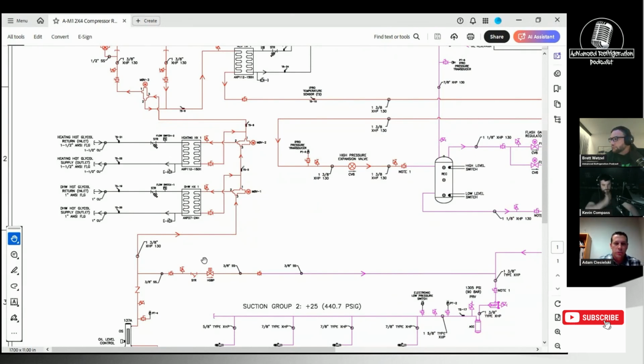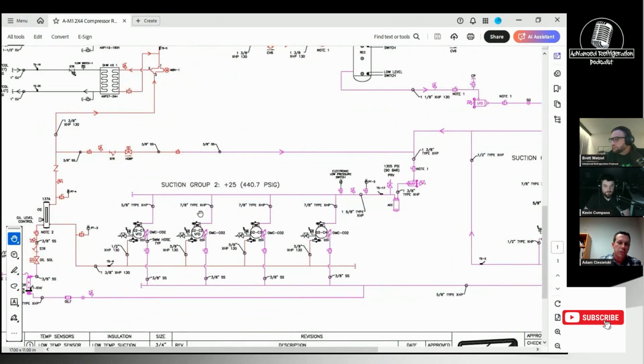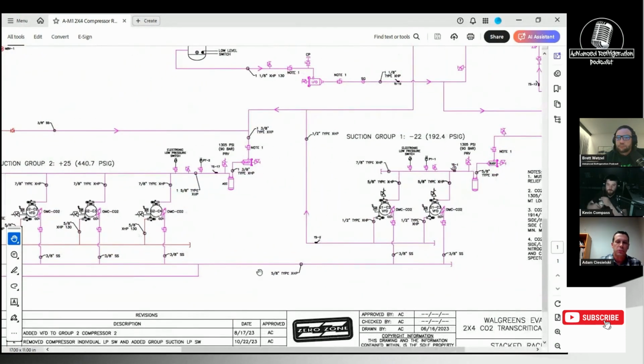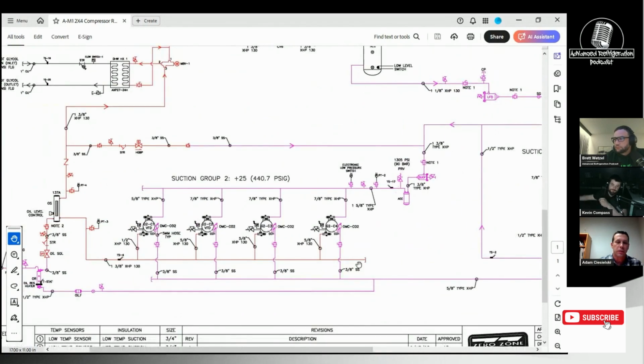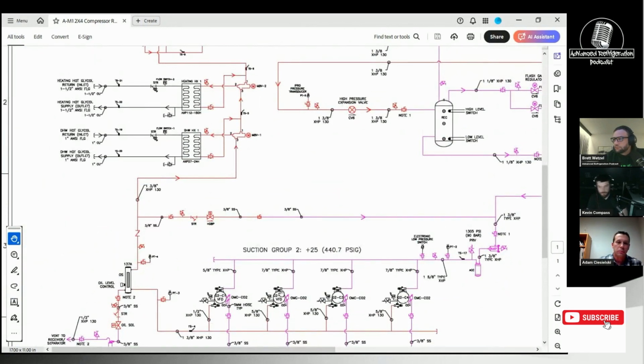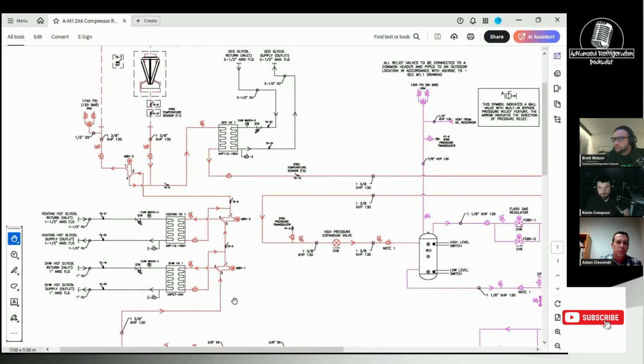So we've got two heat exchangers on this. The refrigeration side of this rack is pretty typical. It's not much different. It's a booster system. We've got a couple of low temp compressors and 4 medium temp compressors, typical booster rack configuration. Where we've got some unique characteristics of this rack is we've got 2 heating loops. This DHW heat exchanger 1 is actually just domestic water, but that is secondary to the glycol heat exchanger that we've got here. From a control sequence, our primary motive is to produce hot water. Then secondarily, if we do have something still to give, then we'll produce hot water for domestic use.